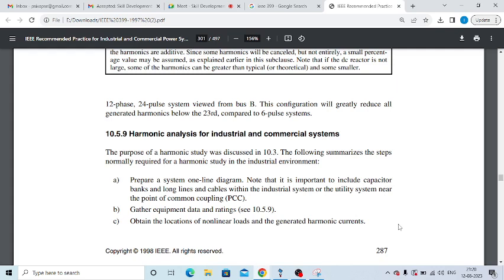As we all know, our power system frequency is 50 hertz or 60 hertz depending on the country. For example, if it is 50 hertz, then the power system parameters such as voltage and current frequency are also 50 hertz. Whenever there is a non-linear load, in simple definition, suppose I am connecting a load to the source, then due to the non-linear characteristics of the particular load, even if we provide a sinusoidal voltage, the load will draw a non-sinusoidal current.